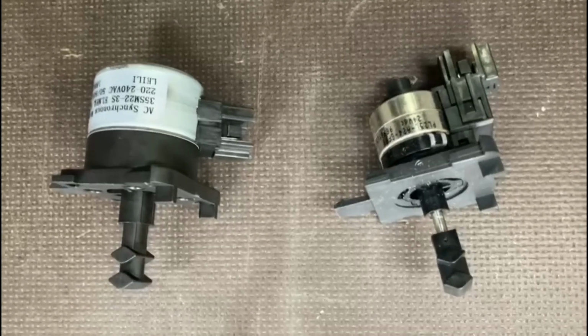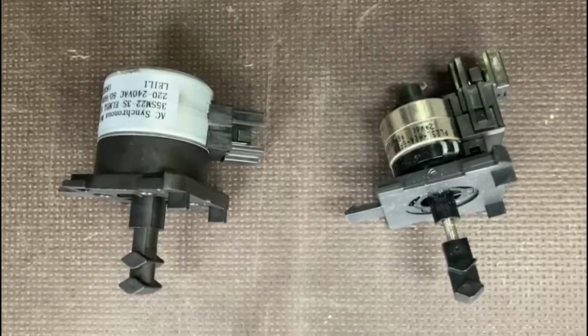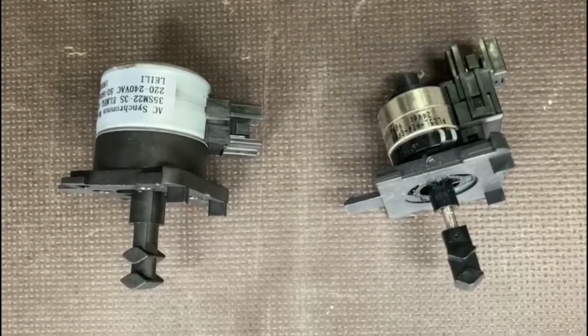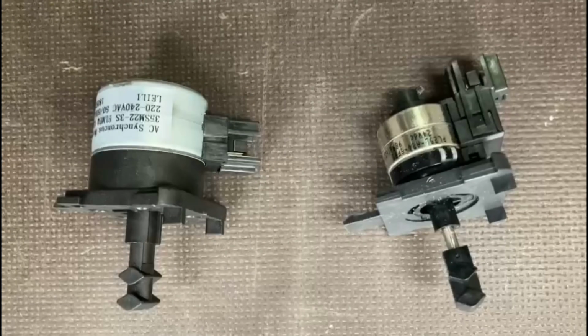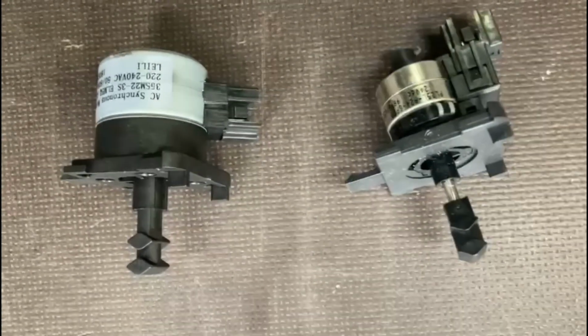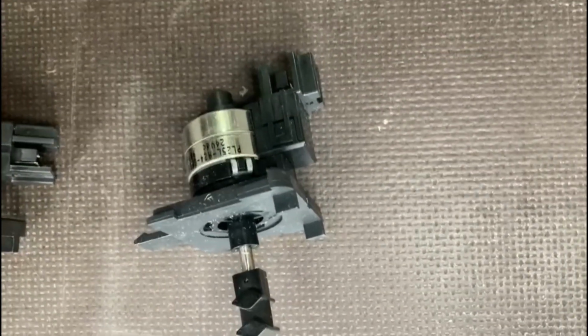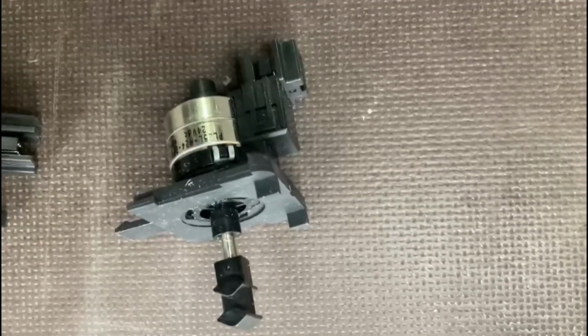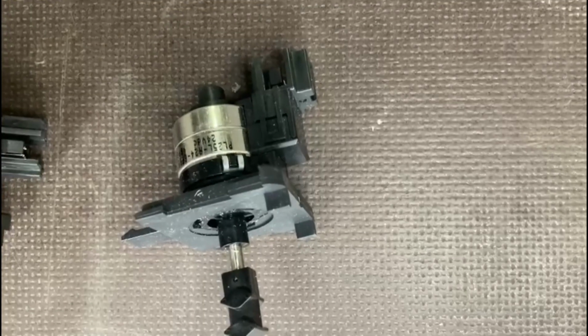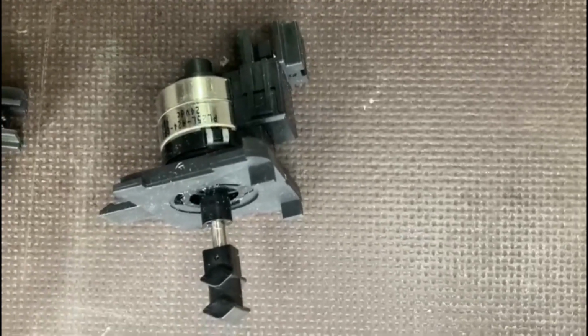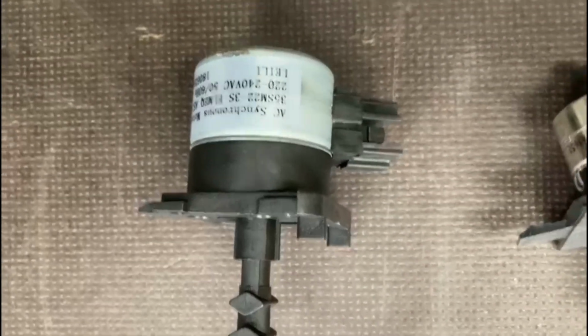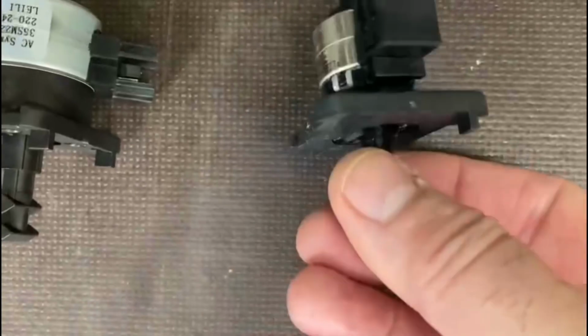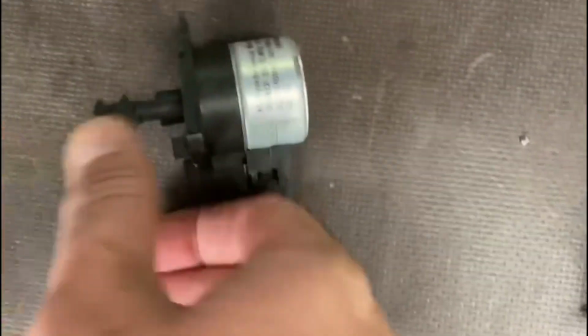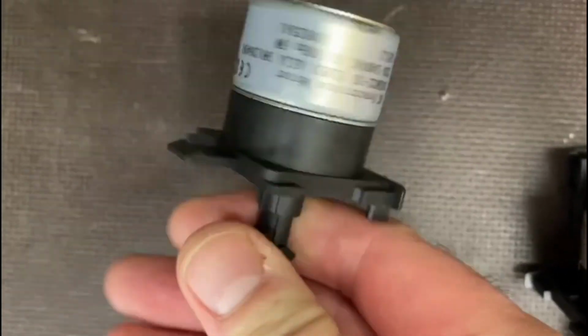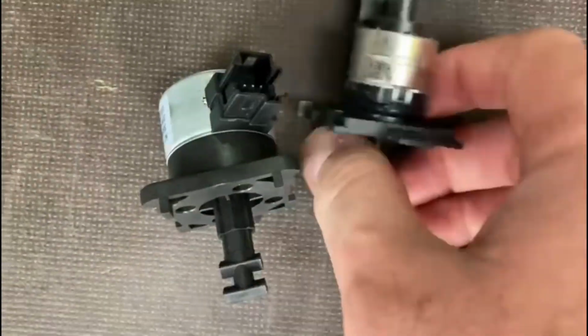So, you know, they can't be interchanged, and people have tried before in the past, and I've got a story about that. But anyway, when you're testing these different motors, or when you're changing them, you've got to make sure the one you take off is the one you put back on, because one will be on the 240 volt side of the circuit board, this one, and this one will be on the low voltage side of the circuit board. So you test them differently and they work differently. A 24 volt motor with a 240 volt supply will probably blow the motor, and a 24 volt supply trying to move a 240 volt motor won't work. They will fit. This will fit on the same paddle as what this does. They have the same fitting. The paddle is the same, but they just won't work.